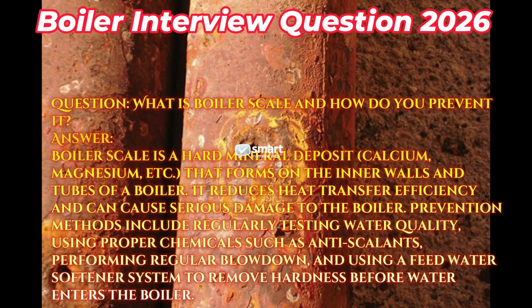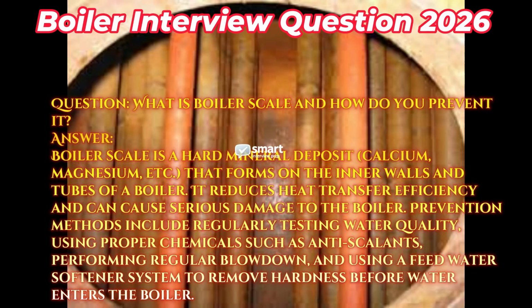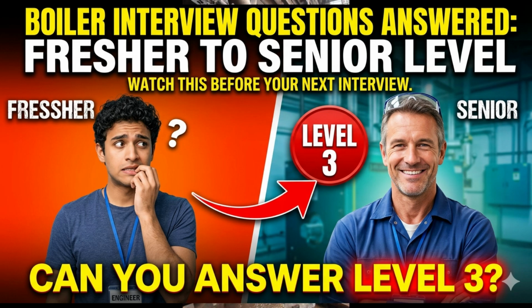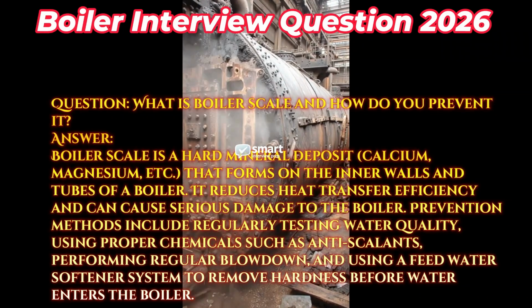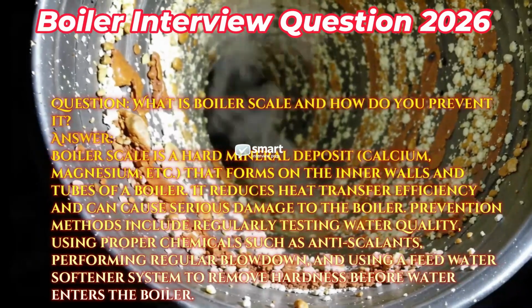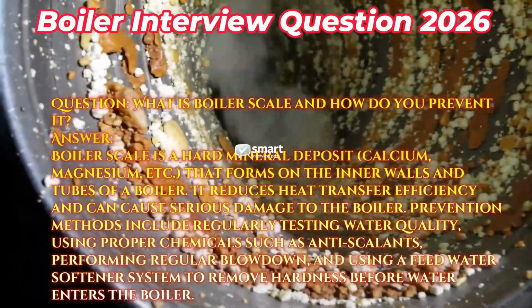Question. What is boiler scale and how do you prevent it? Answer. Boiler scale is a hard mineral deposit, calcium, magnesium, etc., that forms on the inner walls and tubes of a boiler. It reduces heat transfer efficiency and can cause serious damage to the boiler.